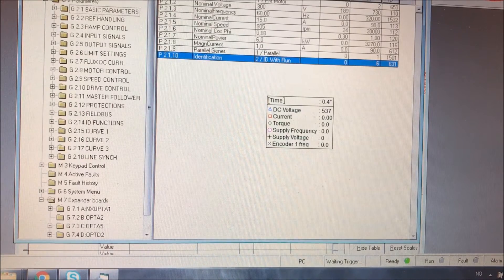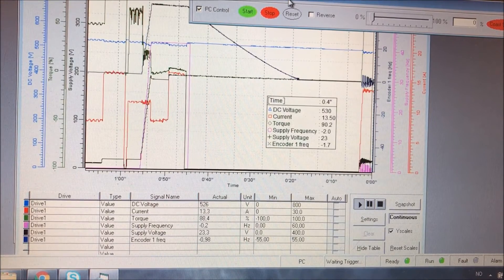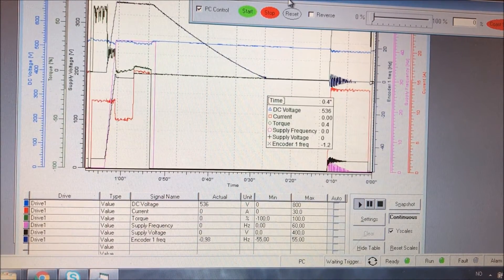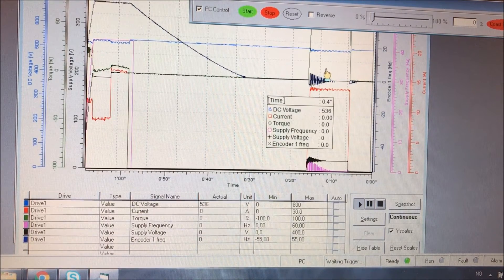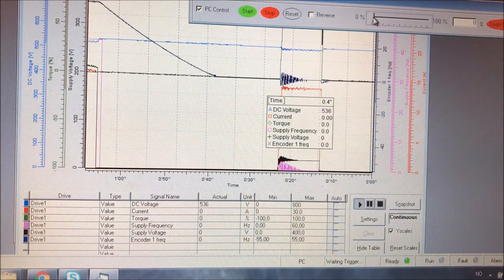Now we verify the encoder signal. We go to identification, select no action, then select encoder ID run. The purpose of this is to find the zero pulse. I hit the start button and it starts doing this strange movement — that is the stator field sweeping over the rotor magnets to find the magnet and its relation to the zero pulse of the encoder.